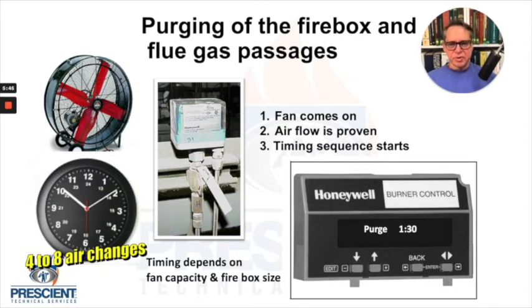So sometimes this is done with a pressure switch. Sometimes it's done with a differential pressure switch. What I'm showing you there in the photo is a differential pressure switch because you see two signal lines going to the pressure switch. So we're looking to have 4 to 8 air changes. NFPA 86 says 4 air changes. If it's a boiler, depends on the type of boiler it is. If it's an NFPA 85 type boiler, the purge time is a minimum of 5 minutes. Gets to be kind of a complex thing with boilers, so you really need to read those pages to understand it. But the timing depends on, of course, the fan capacity and the firebox size.